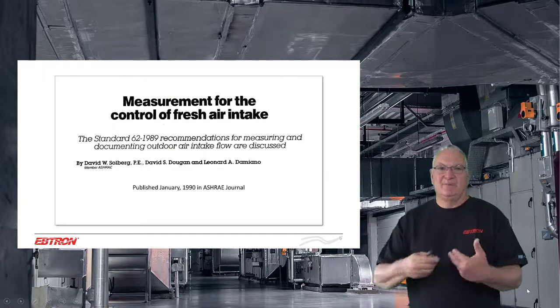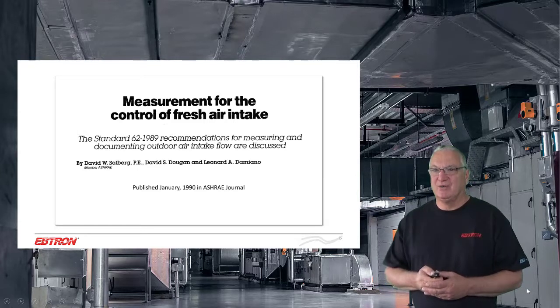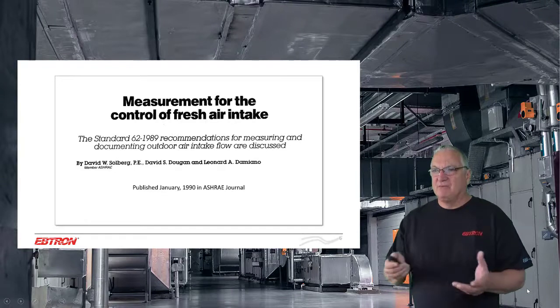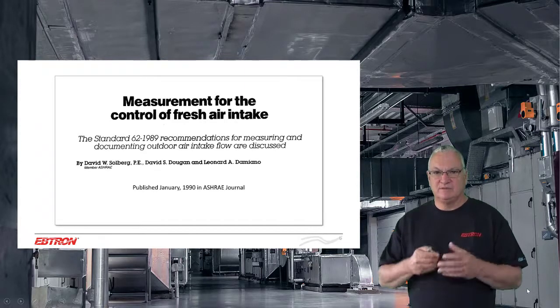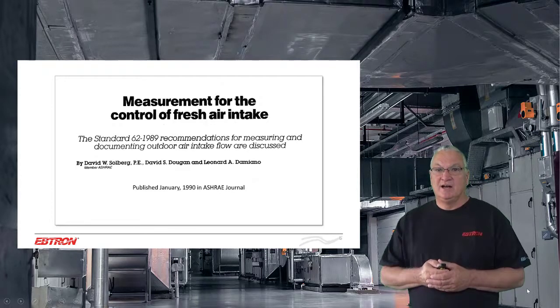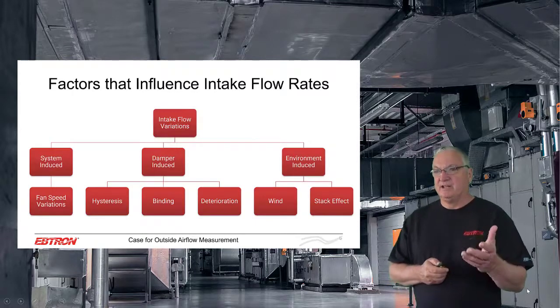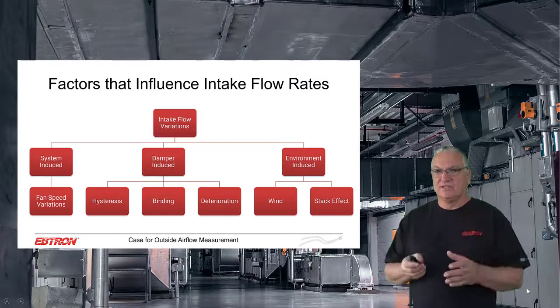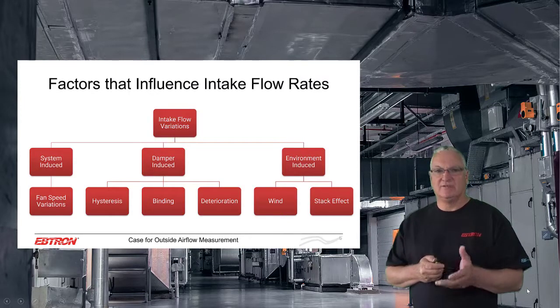We're going to go back to a paper we published 30 years ago — it's still a very important paper — on measurement for the control of fresh air intake. It discusses some of the problems we have to overcome when we decide to be concerned with dilution ventilation, and a lot of the problems we have today really come to light in this analysis. We'll go into detail about what we need: system-induced, damper-induced, and environmental-induced factors that influence outdoor air flow rates.